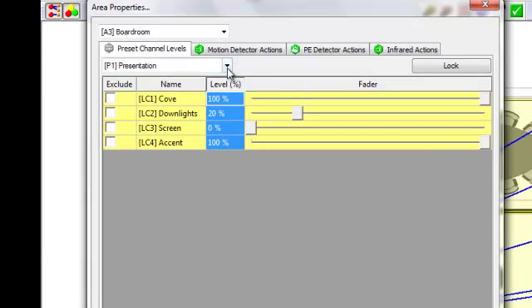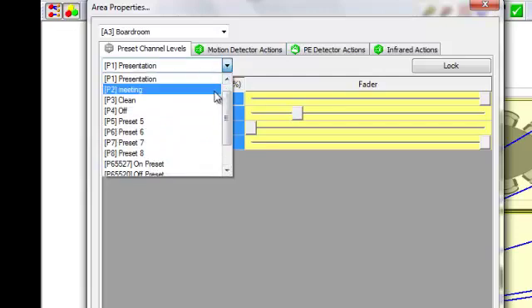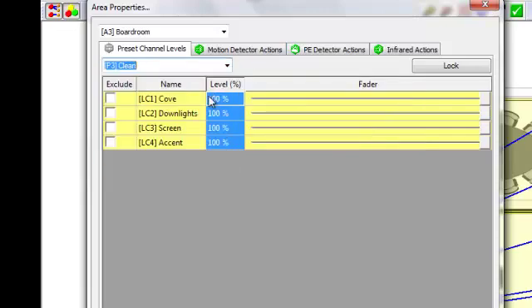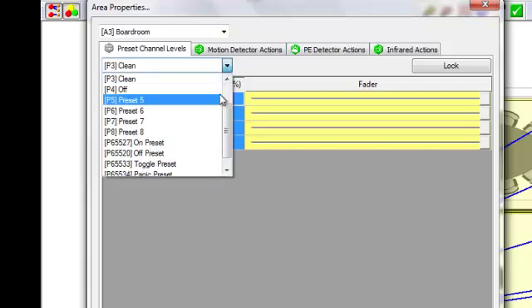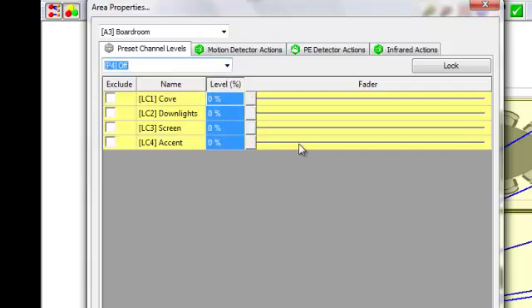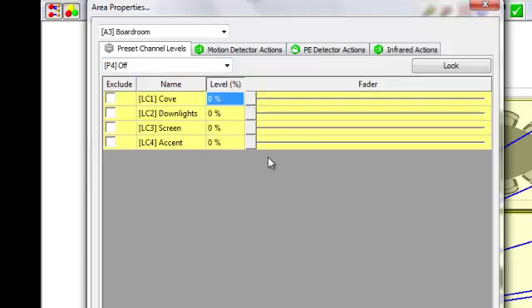And I can simply just drop through my drop down and look at preset 2. Now meeting's a little bit different. I have cove, down light, screen, and accents set at different levels. And now clean, I'm going to want everything at 100%. I need them to see everything so they can clean the best available. And then preset 4, I'm just going to leave it off, so everything's at 0%. So there's how I can go in and move these sliders to adjust the preset levels for each of these scene names.